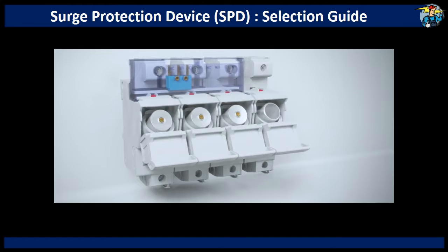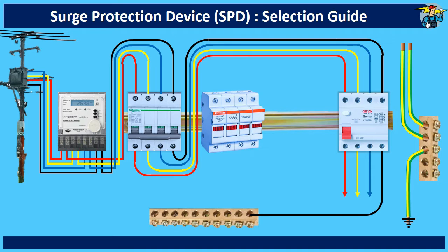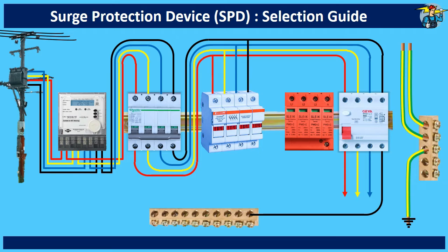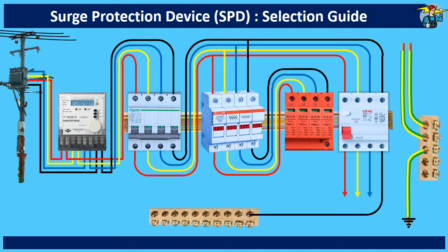According to product testing standards for SPDs, manufacturers are required to declare the SCCR — that is the short circuit current rating of their SPD. Check the specifications on the instruction sheet to find out this value. Then install a type 1 SPD at the entrance of the building, since the power supply is through aerial cables. Connect the main breaker output terminals to the input terminals of the fuse holder. Output terminals of the fuse holder are required to be connected to the four input terminals of the SPD. Then, the protective earth marked as PE needs to be connected to the earth bar. If copper wire is used, the minimum cross-sectional area of this cable for a type 1 SPD should be 16 square millimeters.